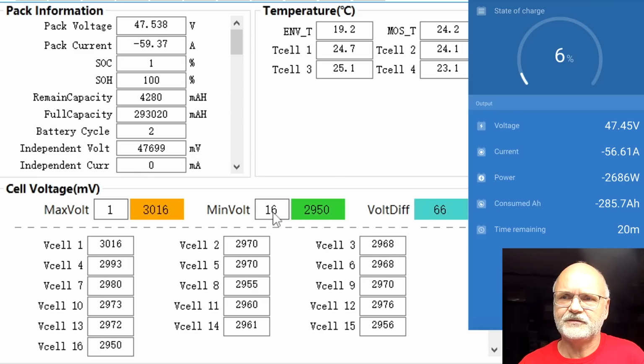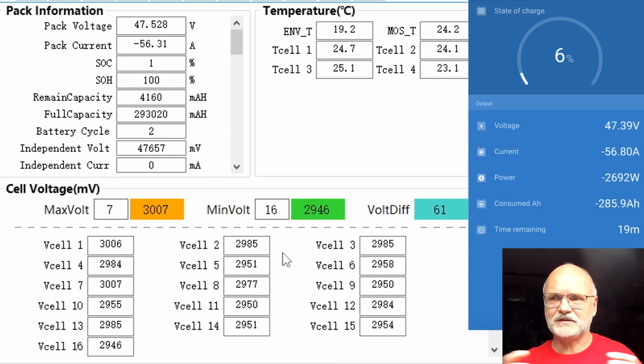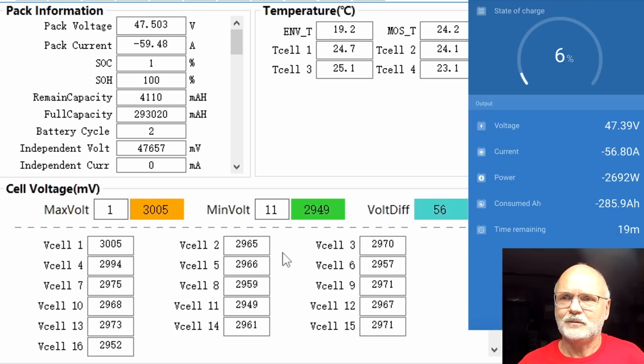Here it is changing 8, 11, 16, which is good, number 9. The more cells are in there, the more consistent our pack is. We only have a deviation of 50 or 70, between 50 and 70 millivolt, which is not bad considering we are at 47.5 volts.